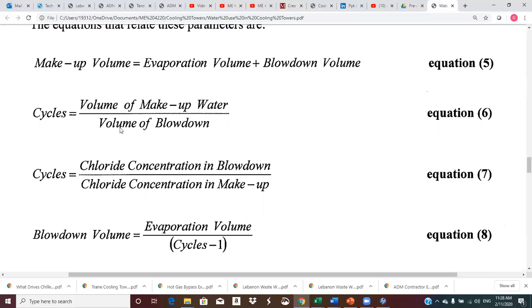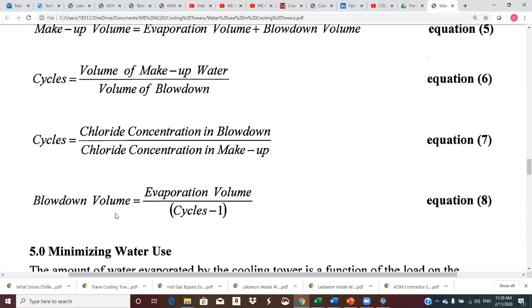Okay. The cycles, we can calculate as the volume of makeup water divided by the volume of blowdown. It could also be done with chloride concentration or some other species. It doesn't have to be chloride. So we measure those concentrations in the blowdown and makeup water, and we calculate cycles. And also the blowdown volume is the evaporation volume divided by the cycles minus 1. You do a little algebra on this, and you can come up with that. Okay.